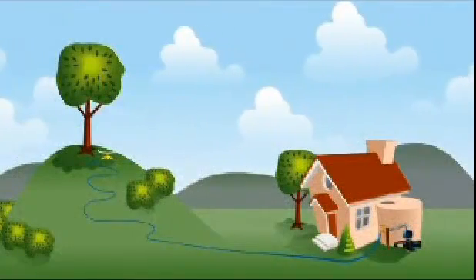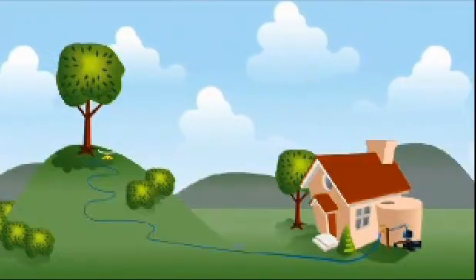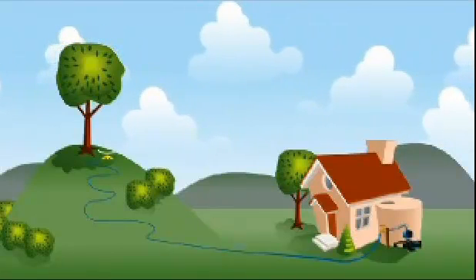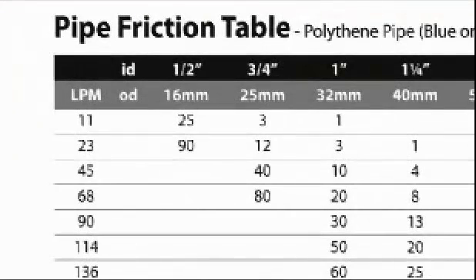Let's see what happens if Aunty Flo uses a larger pipe with a 1 inch inside diameter rather than a 3 quarter inch. Remember, her requirements will stay the same. We go back to the pipe friction table. Only this time, we calculate our friction loss using a pipe 1 inch in diameter. We still need 45 litres per minute.